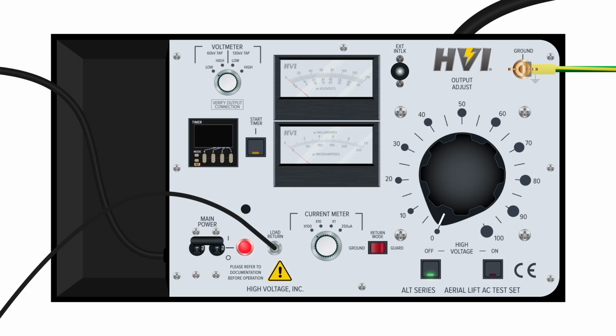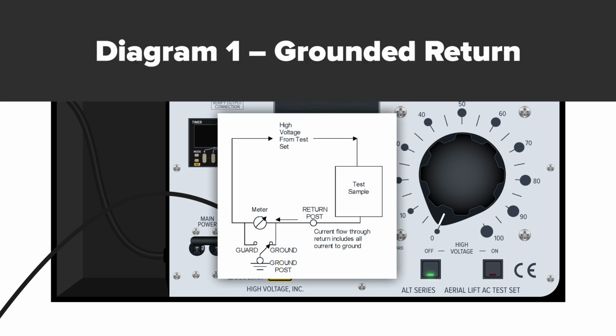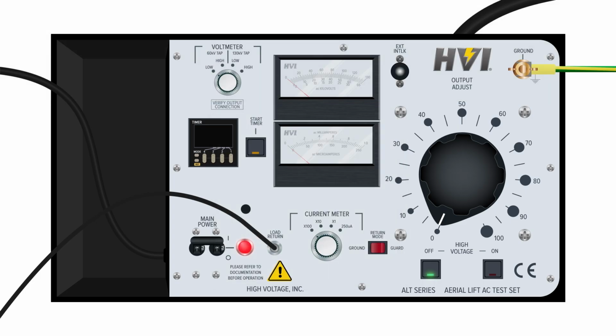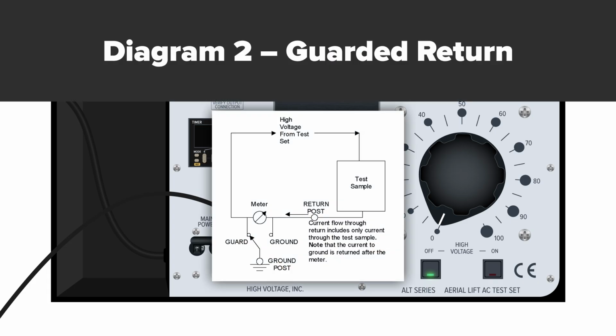When in grounded return, the current meter will read all current to ground, internal and external to the test set. This current might include corona, surface tracking, and shunt resistance. The typical diagram for grounded return operation is shown in Diagram 1. When the output return is set to guarded mode, however, the current meter will only read current through the DUT. The DUT must be isolated from ground on the low side, as shown in Diagram 2. Note that the current to ground is returned after the meter.